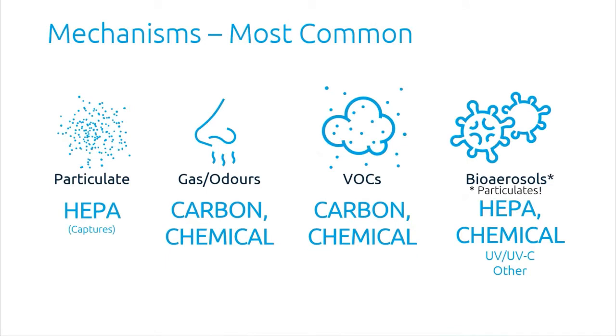So the most common mechanisms, at the end of the day, for capturing particulates, COVID viruses, and all these things: on the particulate side, it's always the HEPA. On the gas, odor, and VOC side—volatile organic compounds that come out of paint, walls, floors, carpet and stuff—it's carbon or chemical media. And for live viruses, microbes, and molds, the HEPA is capturing it, but chemical media can actually kill it. There are auxiliary systems as well that can kill these things we've talked about. So those are the common ones.